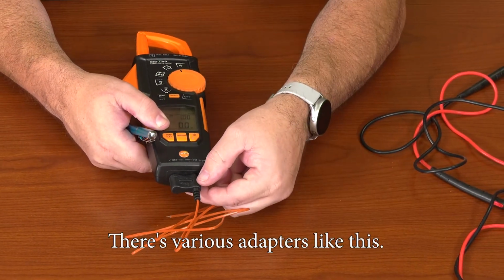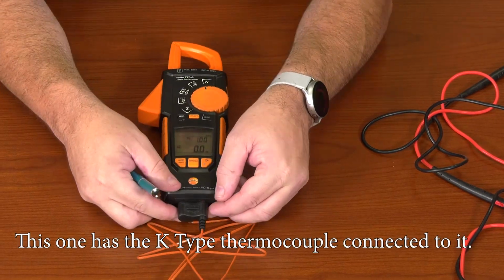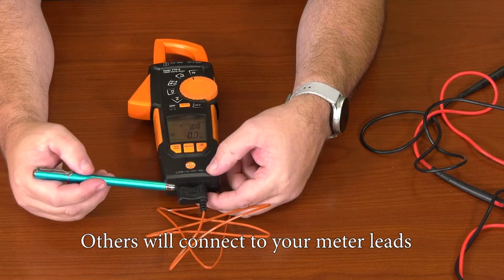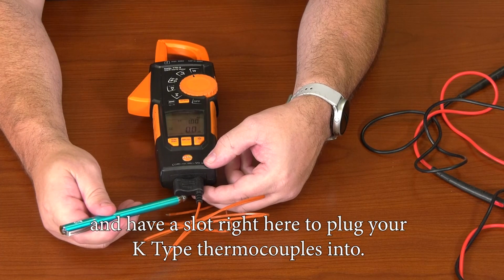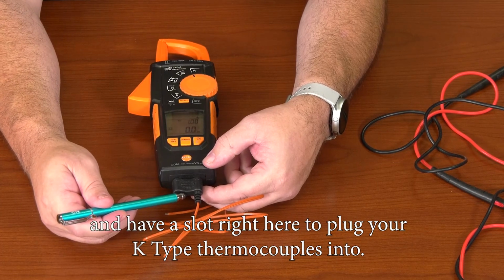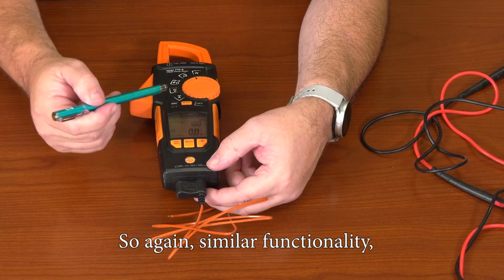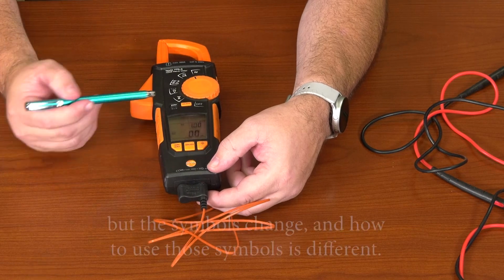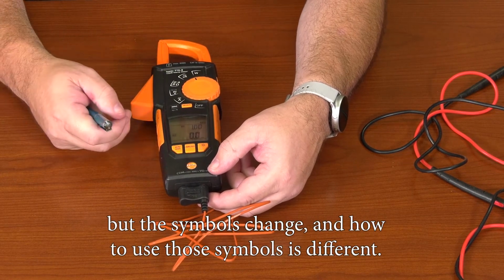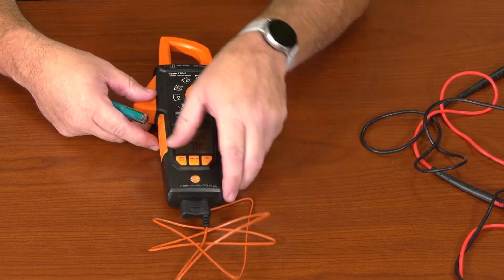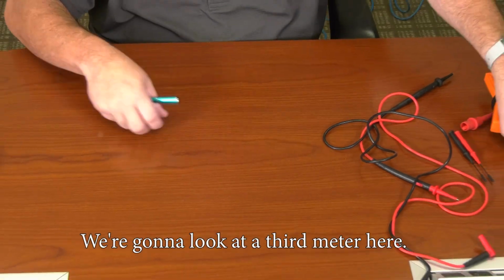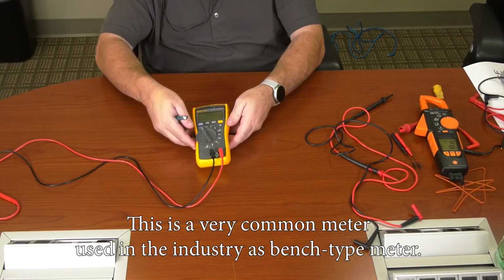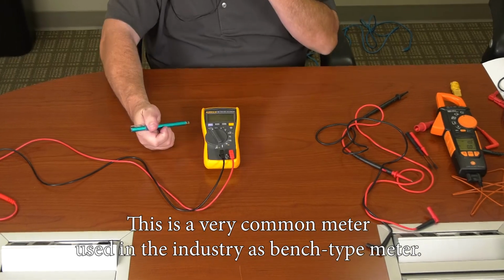There's various adapters like this. This one has the K-type thermocouple connected to it. Others will connect to your meter leads and have a slot right here to plug your K-type thermocouples into. So again, similar functionality, but the symbols change and how to use those symbols is different. We're going to look at a third meter here. This is a very common meter used in the industry as a bench type meter.